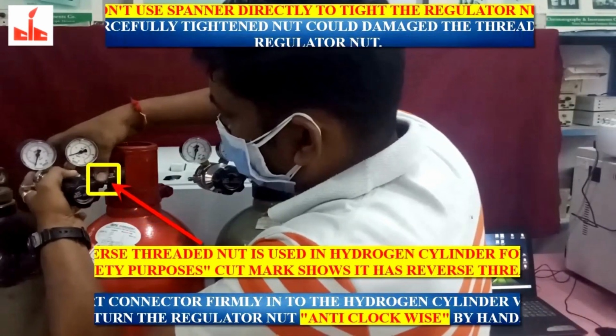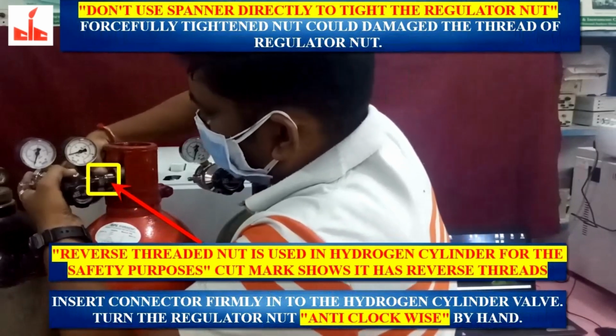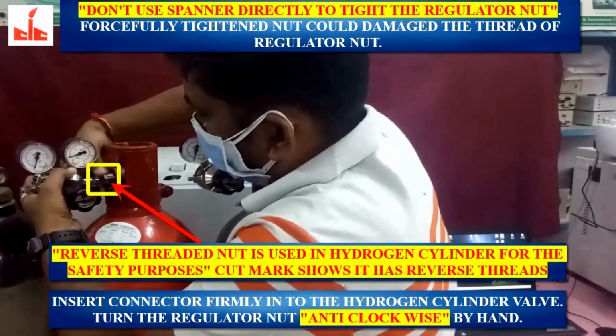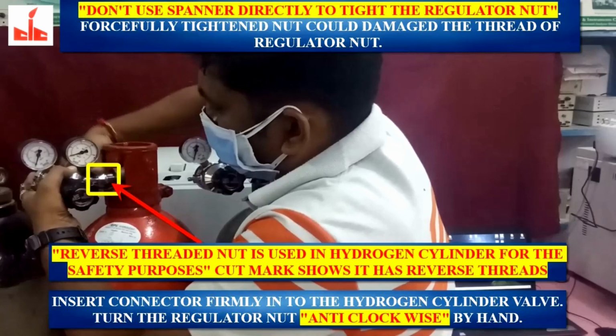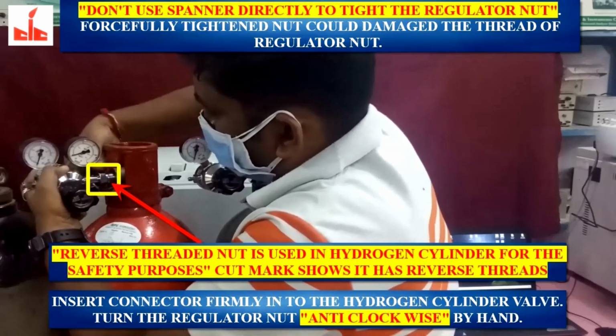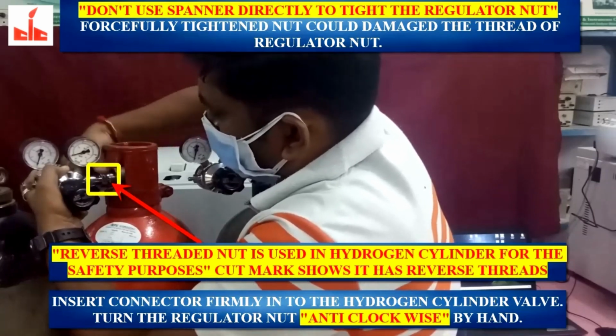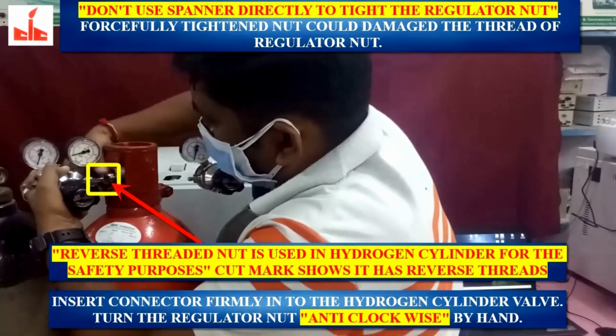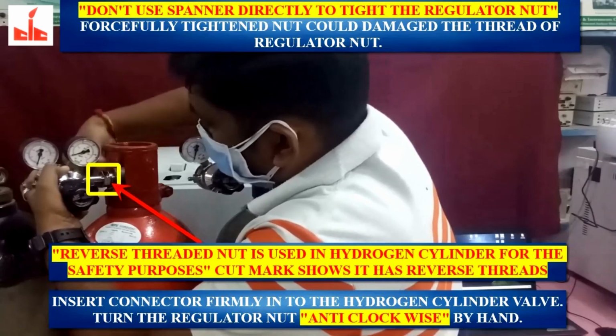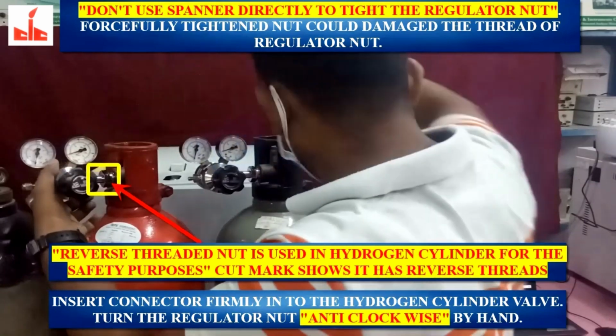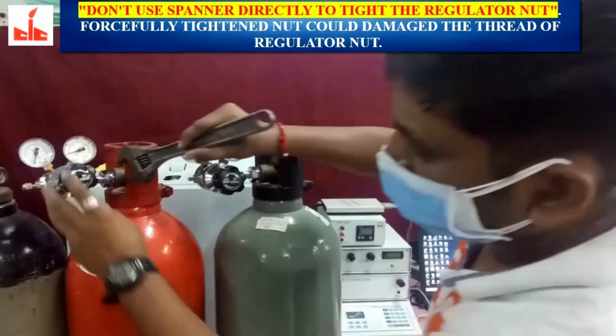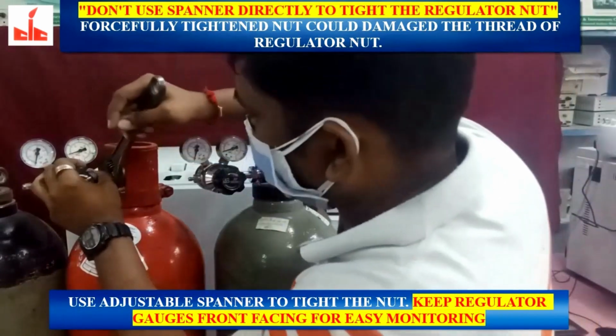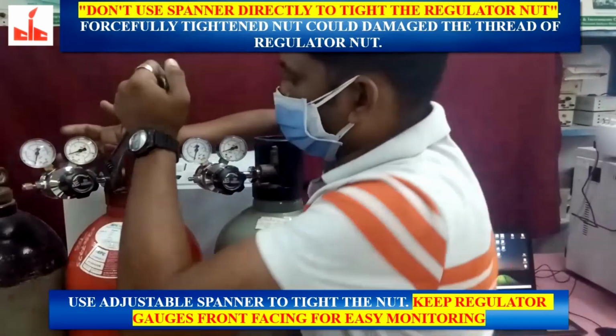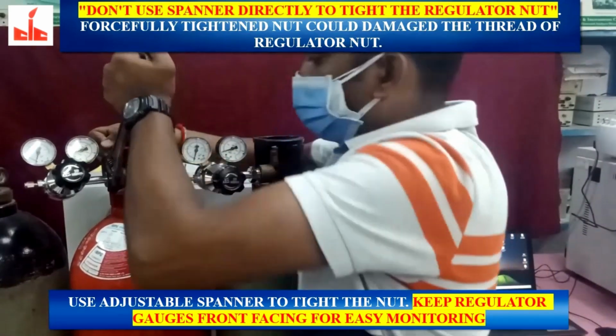Insert the connector firmly into the hydrogen cylinder valve. Turn the regulator nut anti-clockwise by hand. A reverse threaded nut is used in the hydrogen cylinder. For safety purposes, the cut mark shows it has reverse threads. Use an adjustable spanner to tighten the nut. Keep regulator gauges front facing.